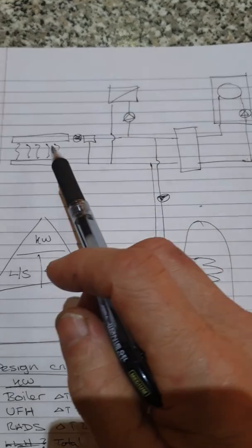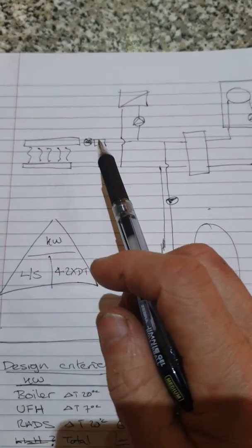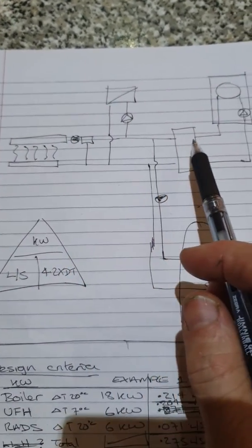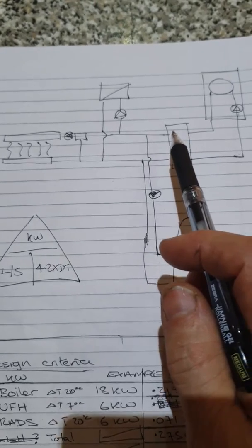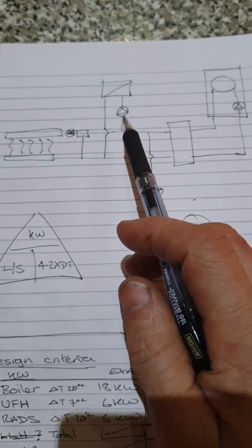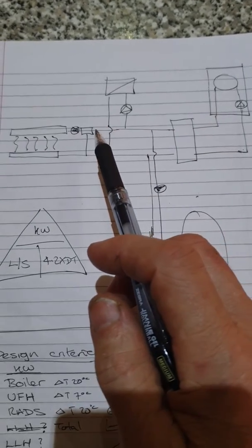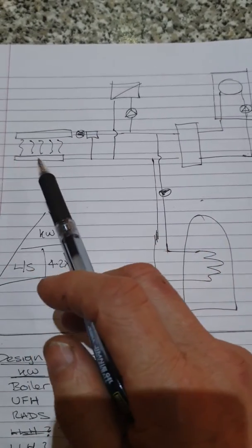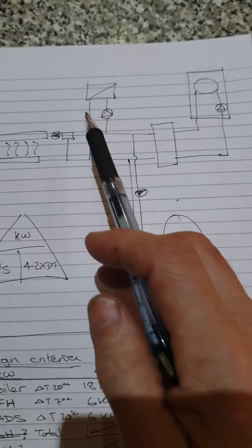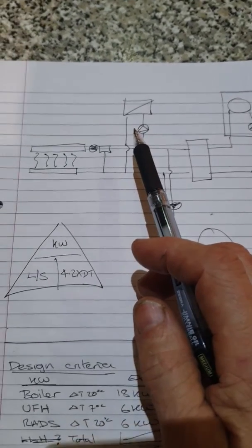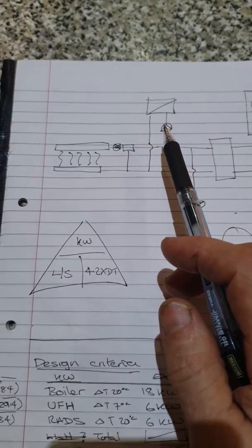Without the low loss header and this pump, the boiler will deliver 20 liters a minute straight to the underfloor heating manifold and straight back up the return, and the radiators will get no heat. I see this very often.